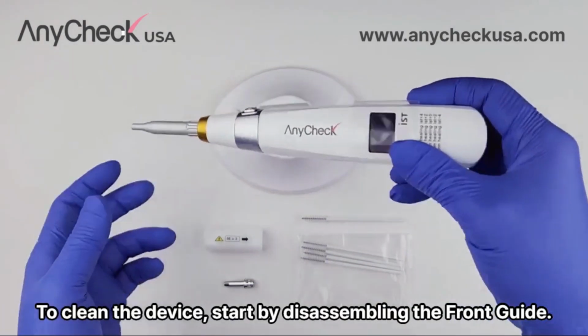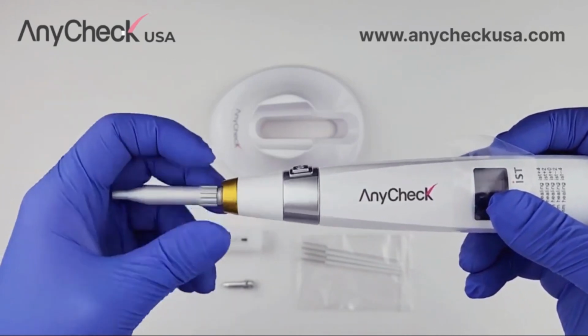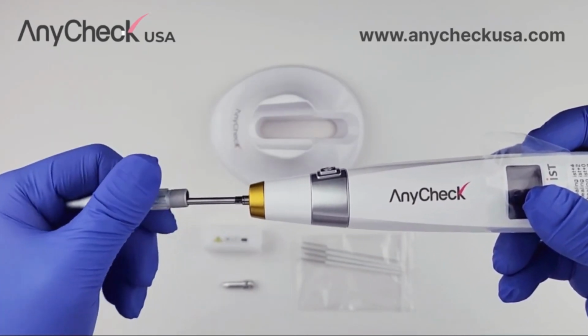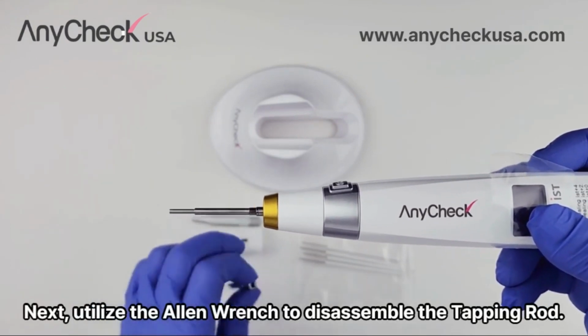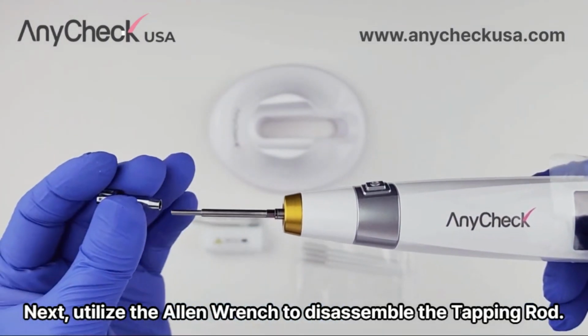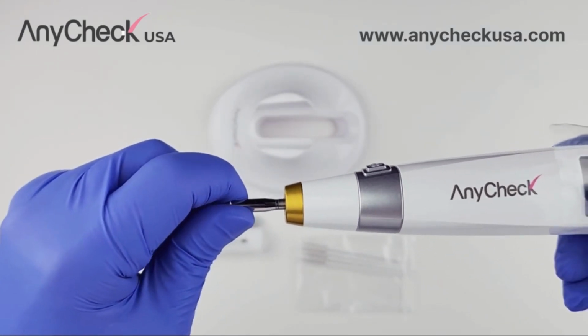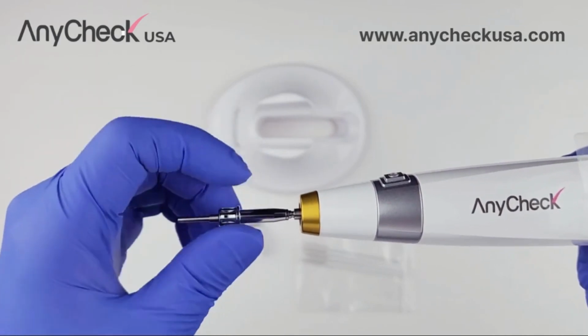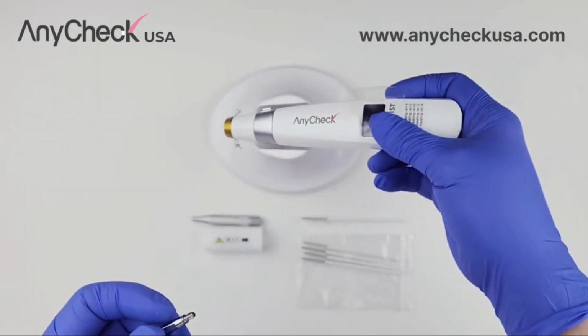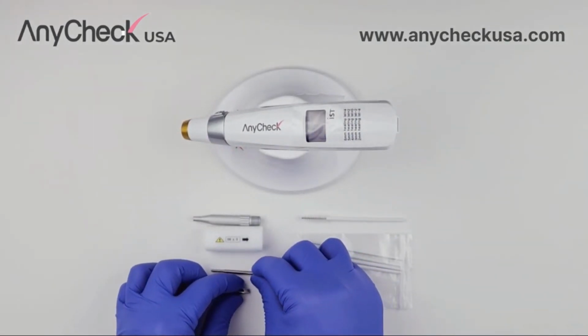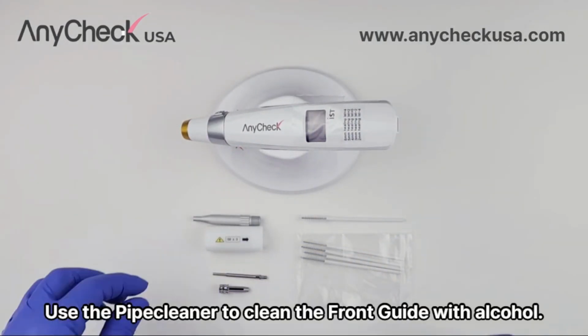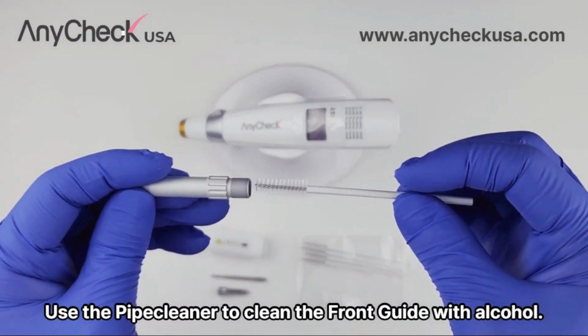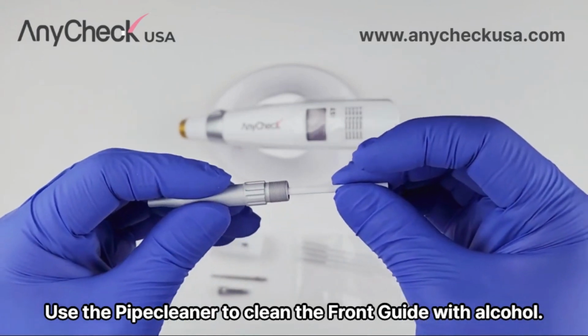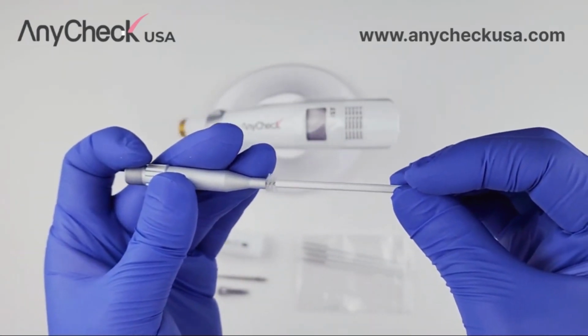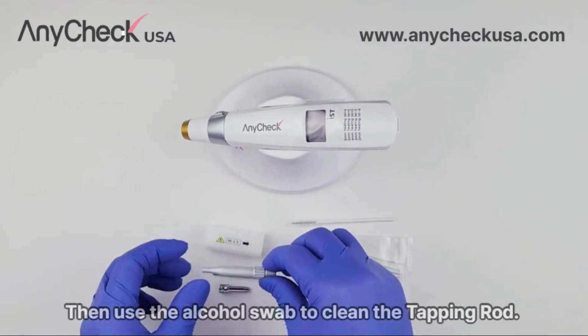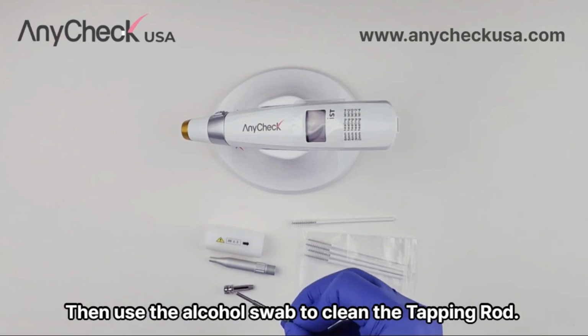To clean the device, start by disassembling the front guide. Next, utilize the Allen wrench to disassemble the tapping rod. Use the pipe cleaner to clean the front guide with alcohol. Then, use the alcohol swab to clean the tapping rod.